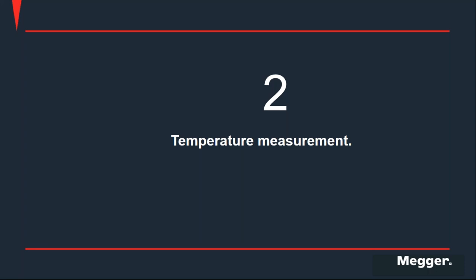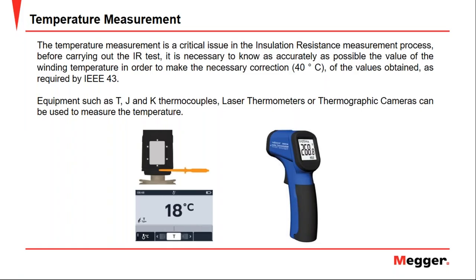Okay, now let's start by talking about temperature measurement. As we all know, and you are here because you have a predictive maintenance focus, any predictive technique is based on two fundamental aspects. First of all, you must have a database that provides a trend. Secondly, the measurements in that database must be made under the same conditions. Therefore, the IEEE 43 standard establishes that regardless of the winding temperature when the measurement was made, all the insulation resistance measurements must be corrected and referred to 40 degrees Celsius in order to have a reference for the measurement comparison. That's why the temperature measurement is so critical for the insulation resistance test.